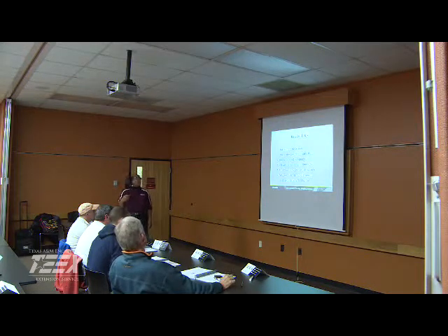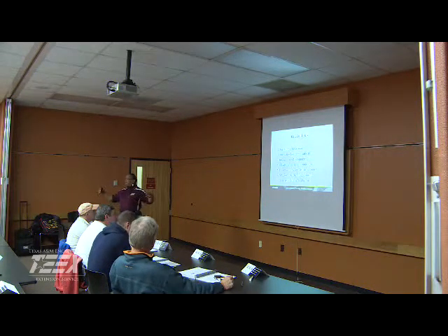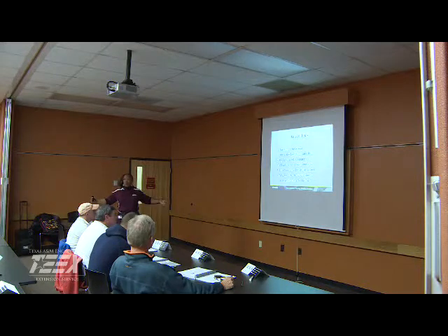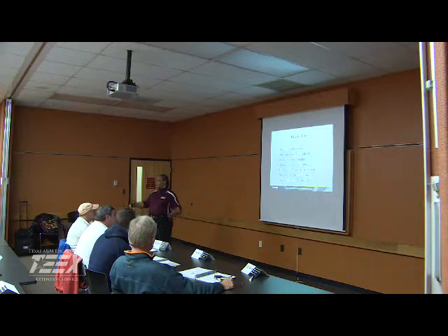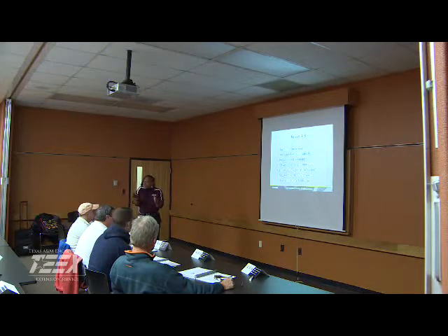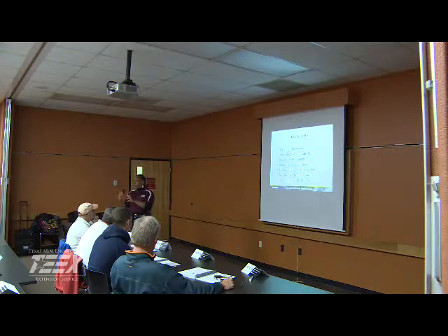So we have the screens, and outside the screen, we're going to put the gravel. Remember that gravel you saw earlier? The purpose of the gravel pack is also to minimize the amount of sand that's being pumped. So it helps us to save on that screen. Because if we get a lot of sand every time that pump comes on, and you've got all this incrustation on your screen, it's going to minimize the amount of water that you're actually able to pump up that well also.